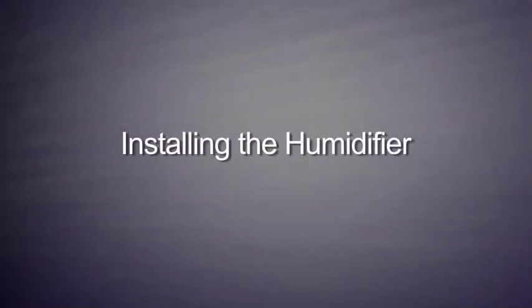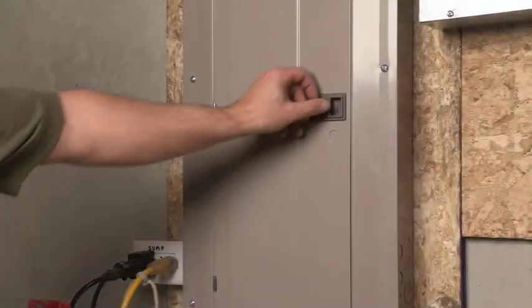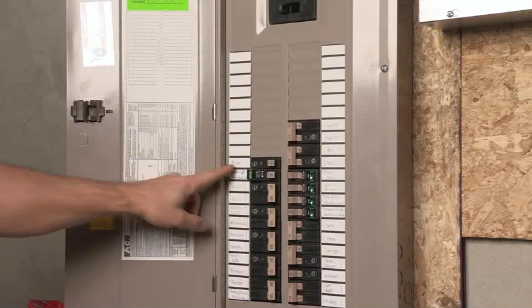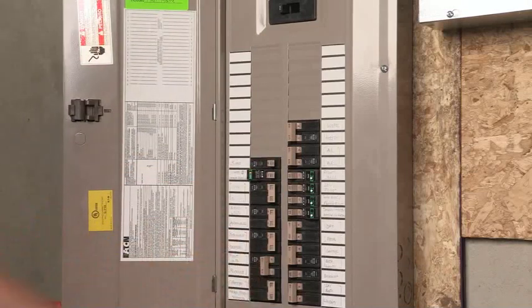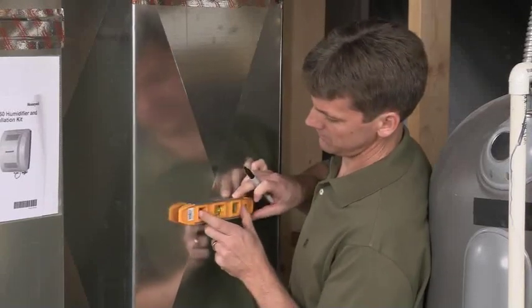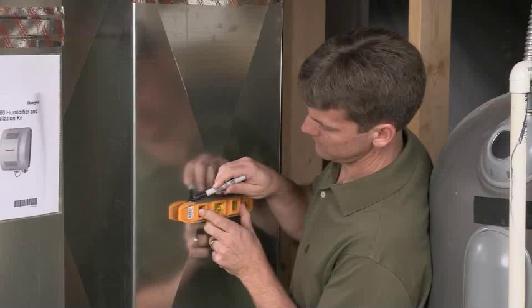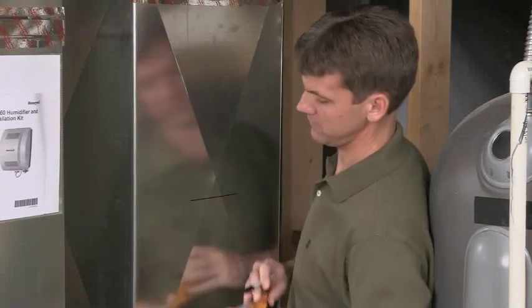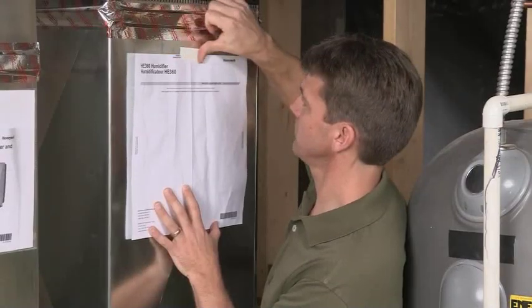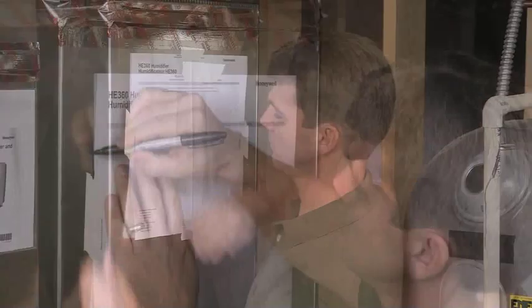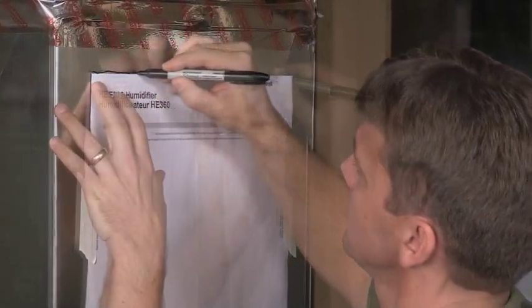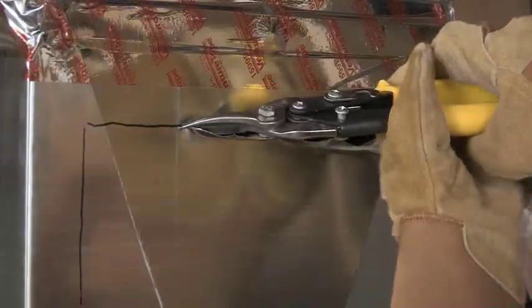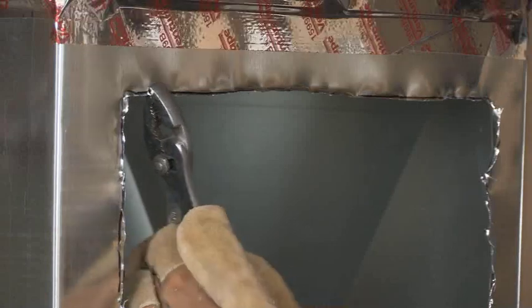Now that you know where you're going to install your humidifier, it's time to get started. First, you must turn off the power to the air handling system at the circuit breaker in order to prevent injury during the installation process. Draw a level line on the ductwork at the bottom of the location you've chosen for the humidifier. Tape the template on the ductwork and trace around it. Remove the template and carefully cut the rectangular opening, using the lines you've drawn as a guide. You can use pliers to flatten the cut edges if needed.